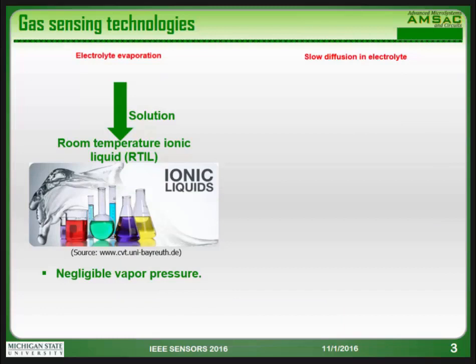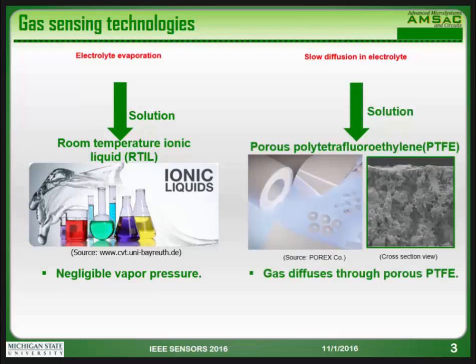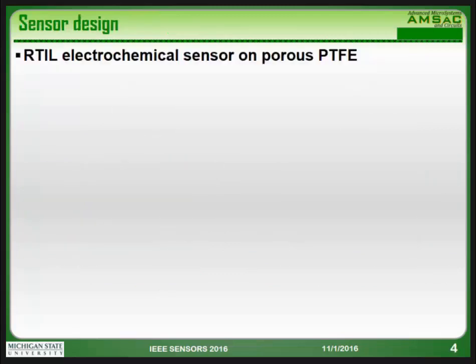The first one is the electrolyte evaporation. We use a room temperature ionic liquid, which is a liquid composed of 100% ions, and this liquid has negligible vapor pressure, which means this liquid cannot evaporate. And the other problem is the very slow diffusion in the electrolyte. So we're trying to use a porous substrate, which means the gas can diffuse through the substrate instead of through the electrolyte. By this means we can improve the response time. Based on these two solutions, we propose this room temperature ionic liquid electrochemical gas sensor on a porous PTFE substrate.